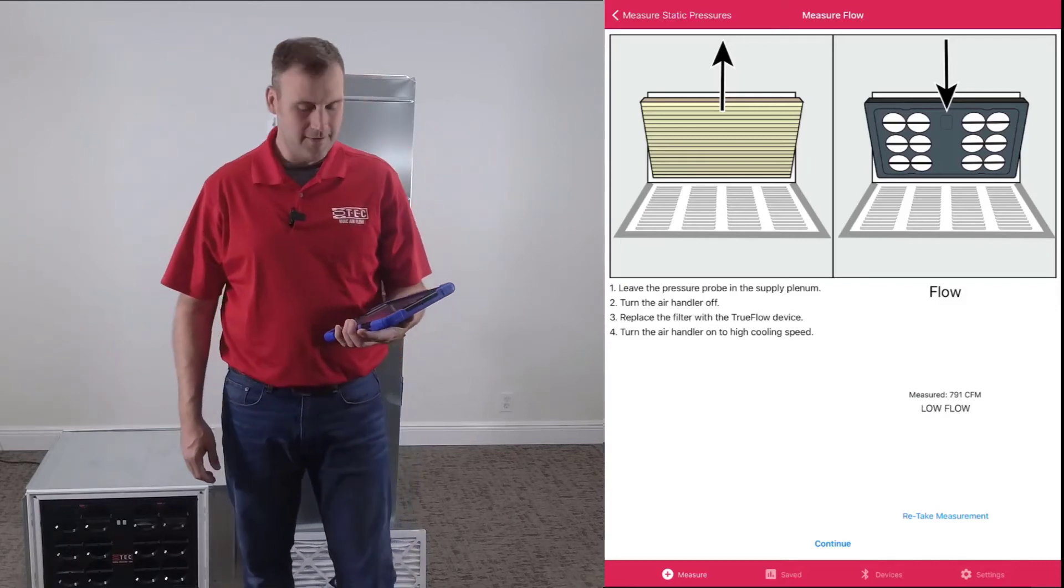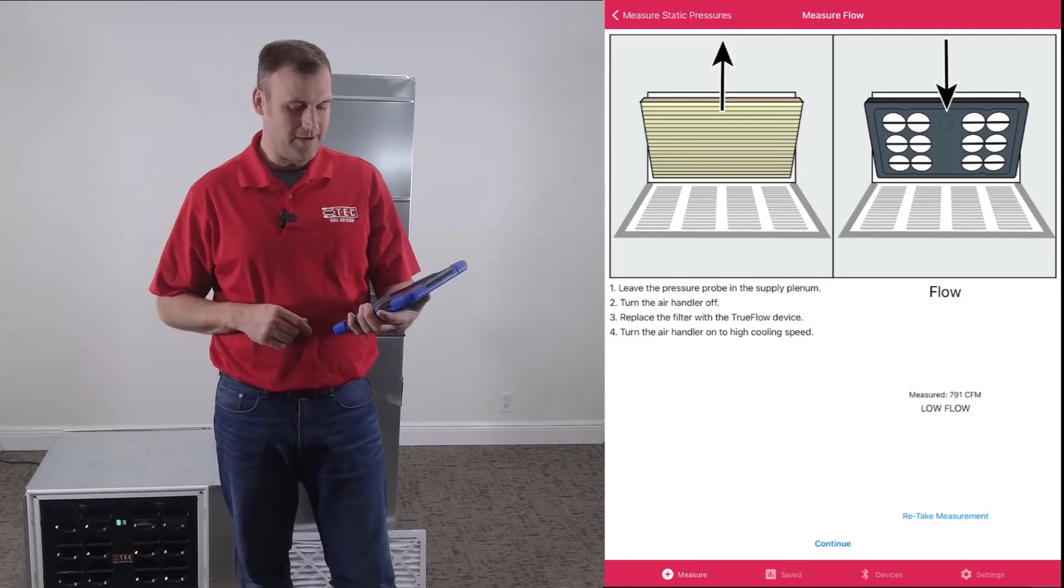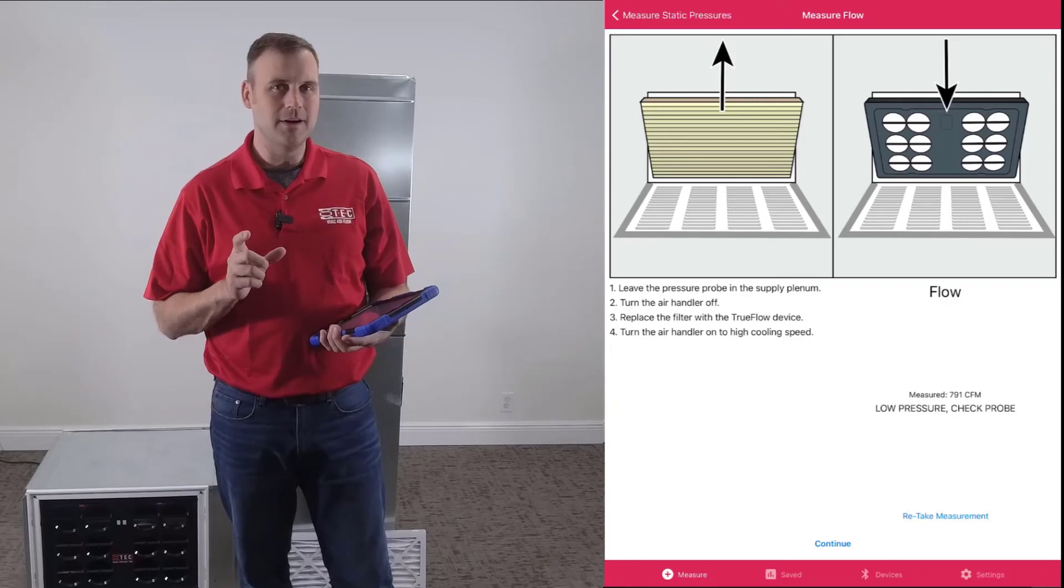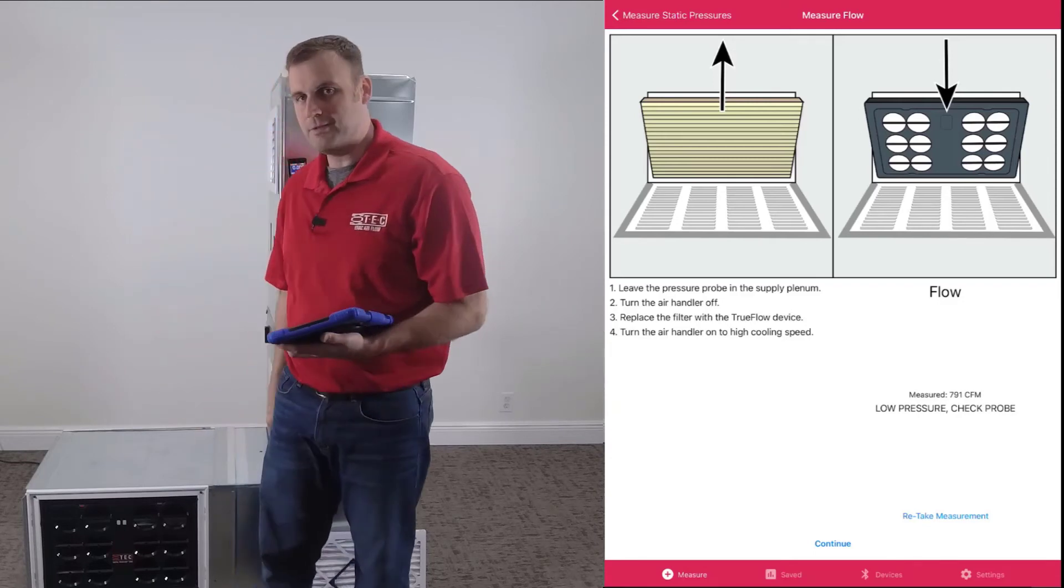Now turn the system off. We have measured 791 CFM. That is the measurement of air moving through the system when the filter was in place.